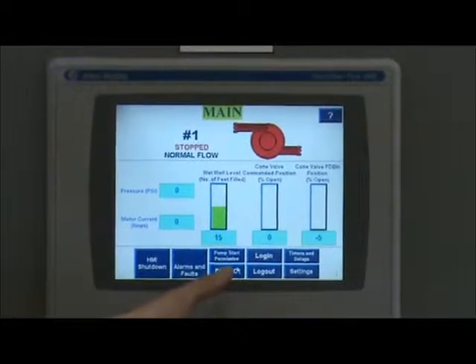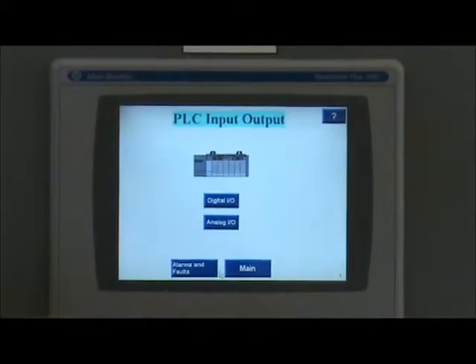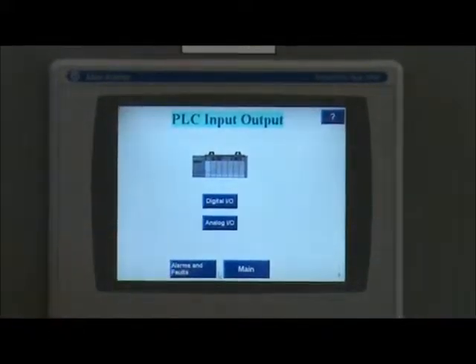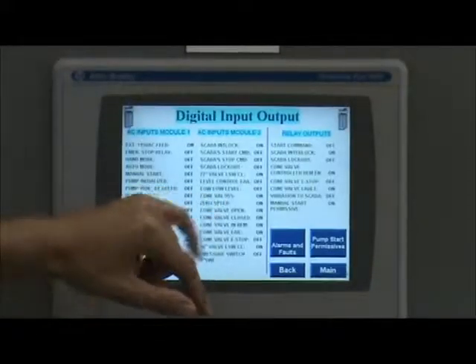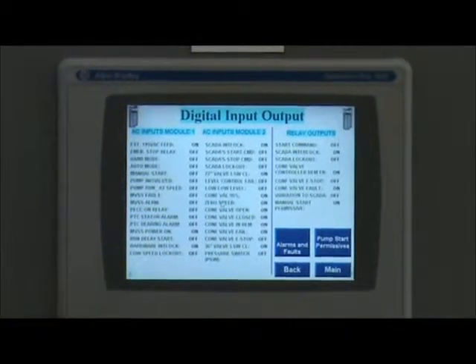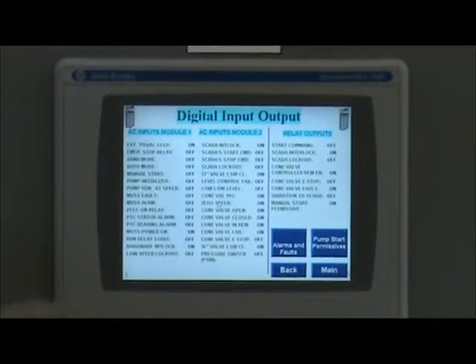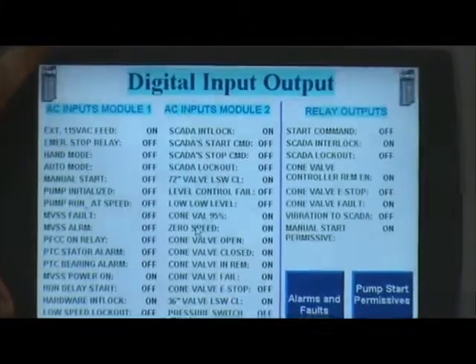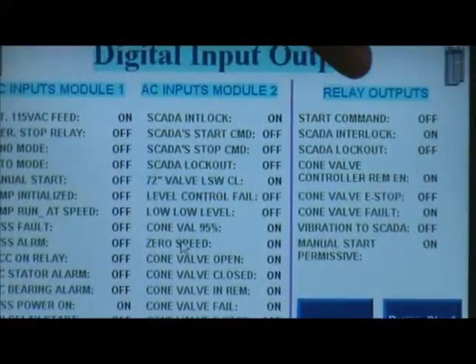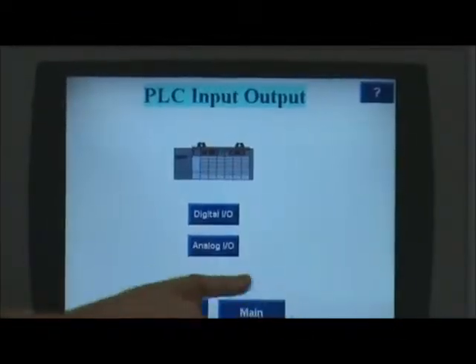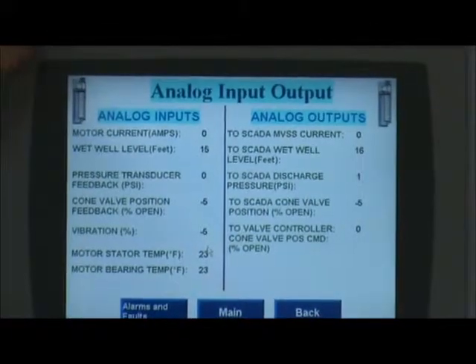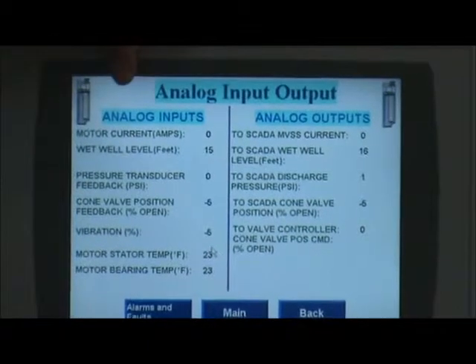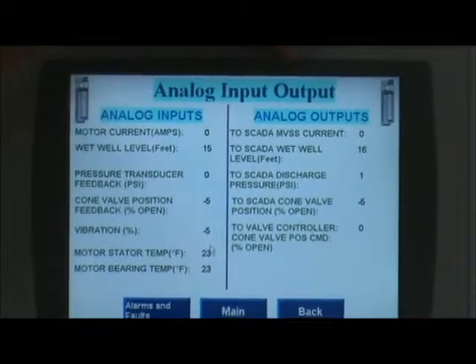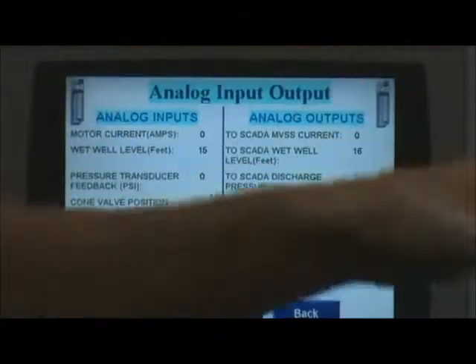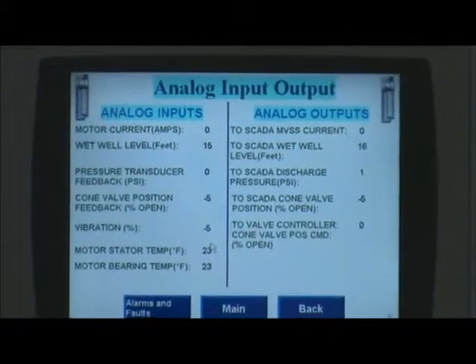The next screen is our PLC I/O. Then you can choose between digital I/O and analog. With the digital, it shows the status of all our input relays, of both modules, as well as our outputs. Through the analog, you can see the level of our 4 to 20 signals that we take in, as well as what we are outputting to the SCADA system and the cone valve position.